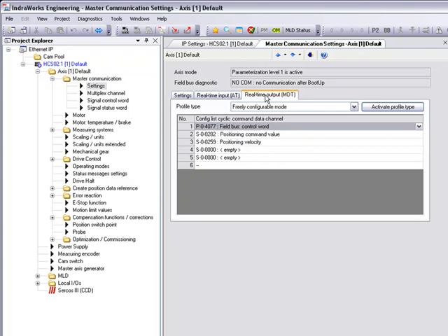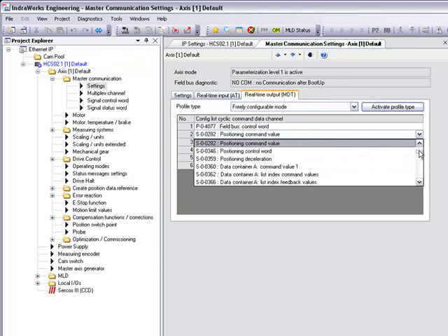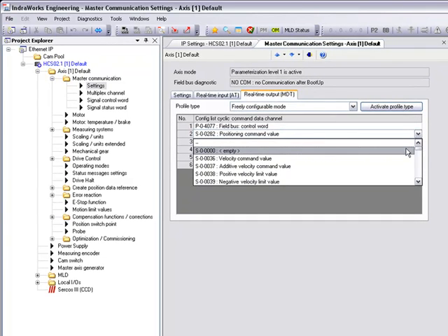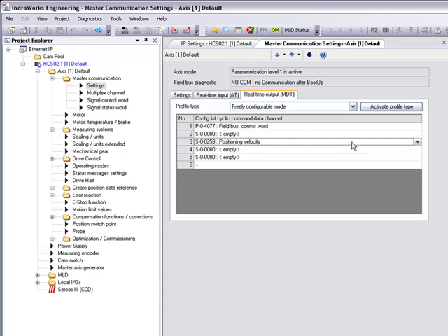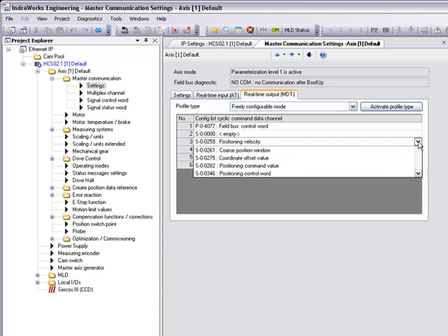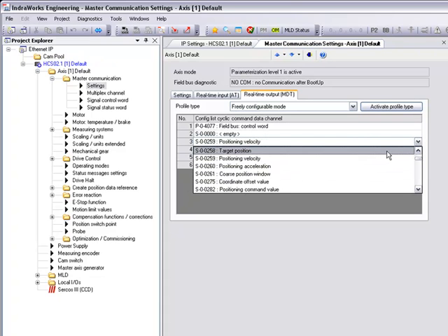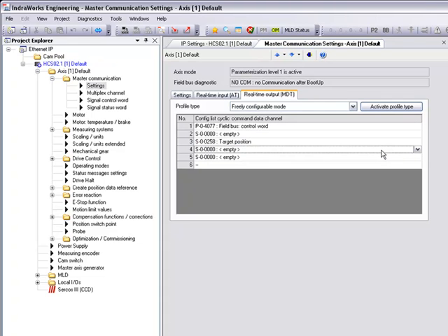Our real-time output is information that the PLC will be sending to the drive, such as our target position, our acceleration, our deceleration, and our positioning velocity. It should be noted that the field bus control word is also a 16-bit word and will require an empty slot behind it.